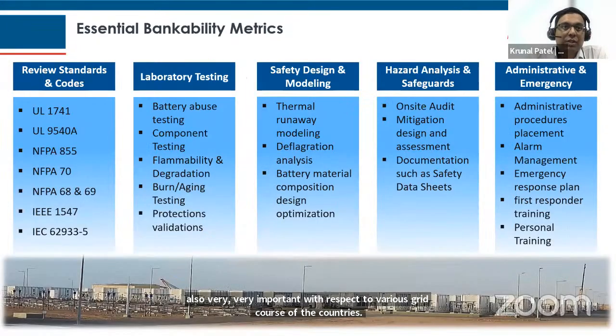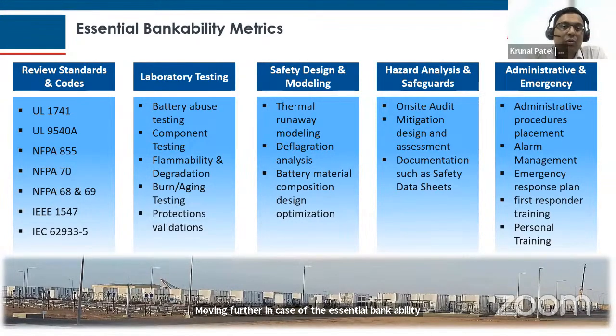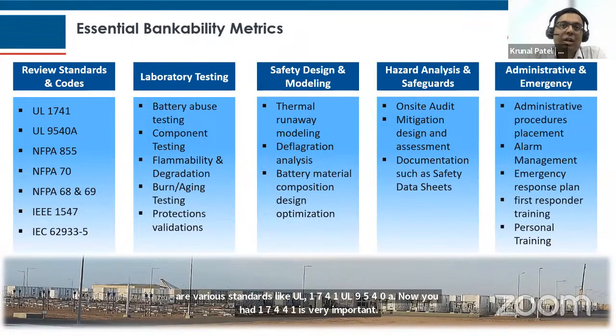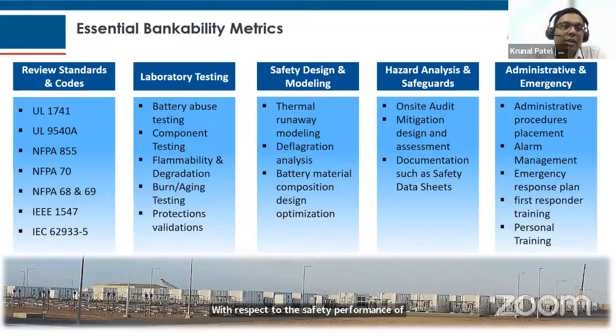Moving further, in case of the essential bankability metrics, there are 5 pillars we identify, where I will not go through too much detail, but at least review standards and codes. There are various standards like UL 1741, UL 9540A. UL 1741 is a very important standard with respect to the safety performance of the power electronics, that is inverters. UL 9540A is very important with respect to the battery cell. NFPA 855, which covers safety related aspects. NFPA 70, 68, 69. IEEE 1547, very important standards with respect to connectivity to the grid and requirements to be fulfilled by the grid, harmonics related studies, and likewise.